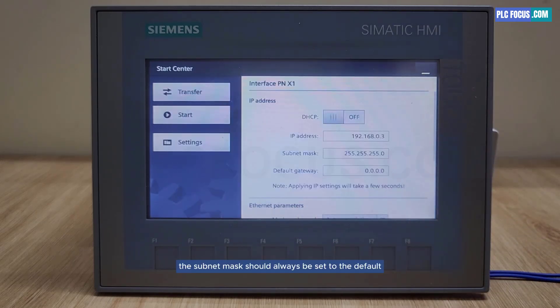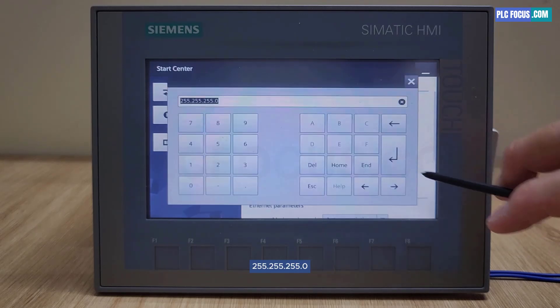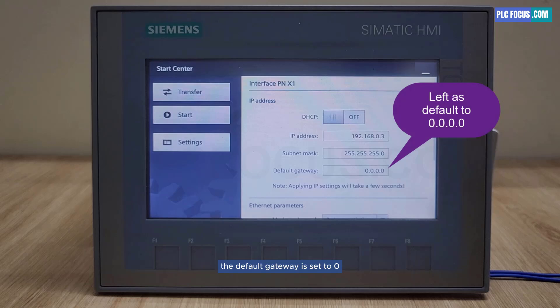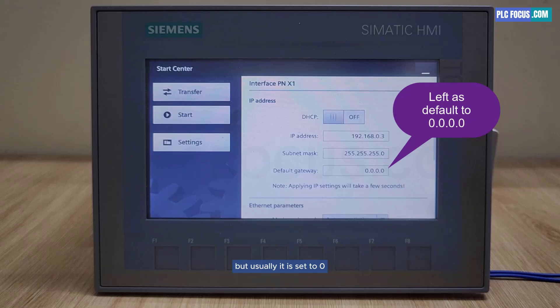The subnet mask should always be set to the default value of 255.255.255.0. The default gateway is set to 0. In some cases, if you connect the HMI to the PLC via a router, the gateway is the IP address of the router, but usually it is set to 0.